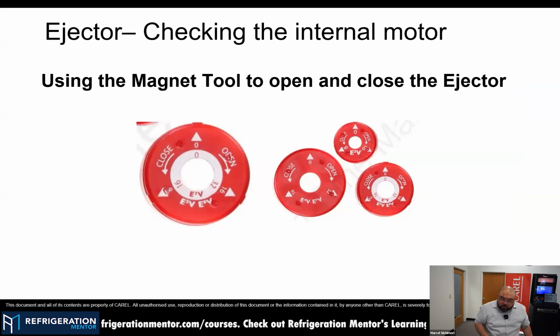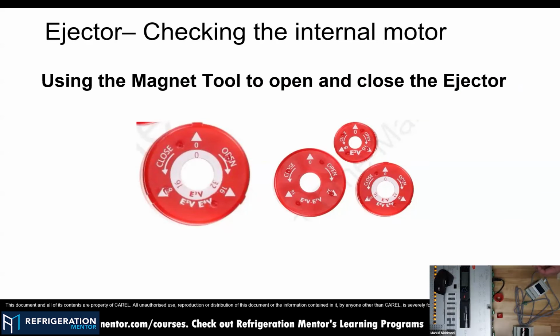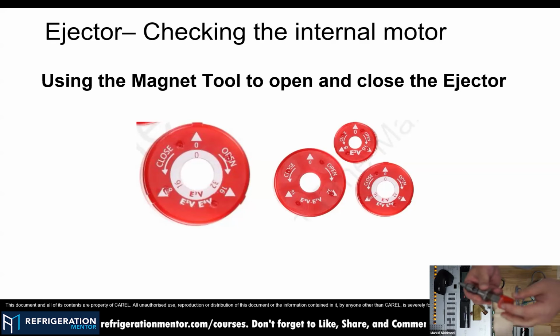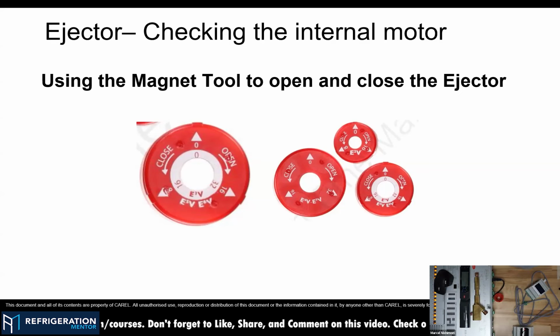Another tool that is quite useful, let me go back to the camera, is the magnet tool. Again, this is a bipolar motor. If you need to make sure that, for example, the motor inside the ejector is not locked and is not broken, what you can do is use the magnets. The same magnets that we use for the electronic expansion valve, you can use to drive the ejector. Running to one side, we are closing. I don't know if you can hear the sound here. This click means that we came to the end of the course of the motor, and to the other side the same.